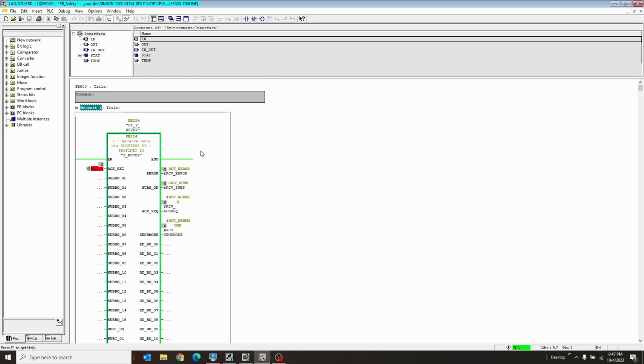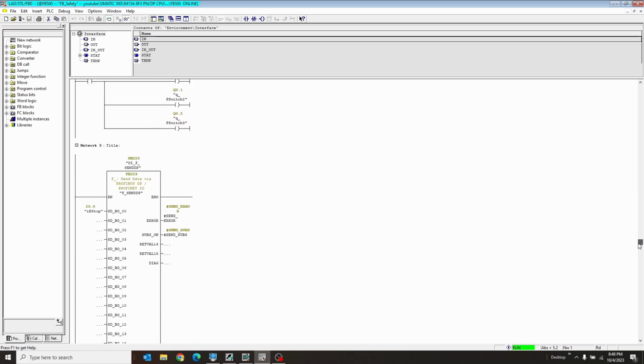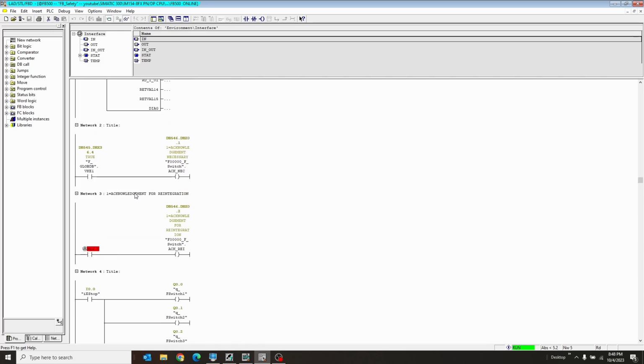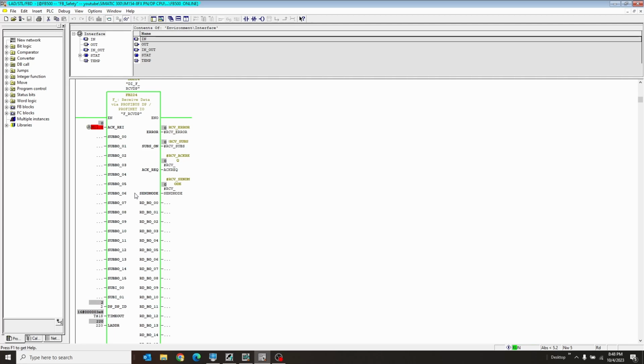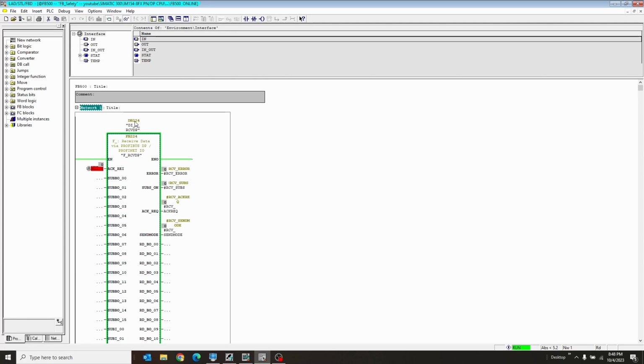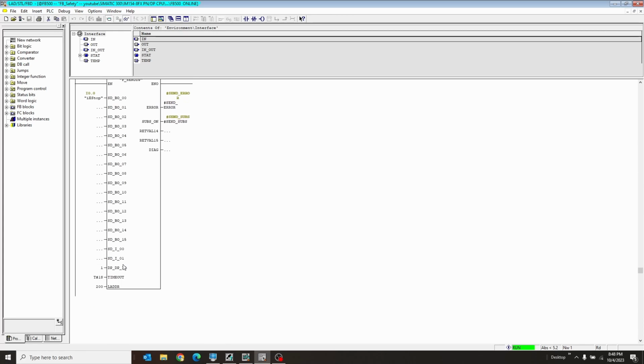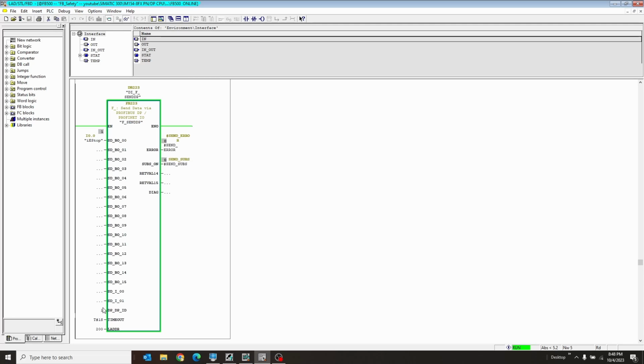I have the FReceiveDP at the top of my safety call, and then I have my regular logic in between there, and then I have my SendDP call. Now, what I want to show you about this guy is that on the ReceiveDP call, you have a reset right here for reintegration, and then you have on this side the bits that would come in for receiving, and I'll show you that in a minute on the other one. But what's important here is this ID here, the ID has to match the send to the receive. So if the receive on this guy is 2, then the send on the other one has to be 2. And likewise, down here on the send, I have a 1 on this guy. So the receive on the other end has to be 1.